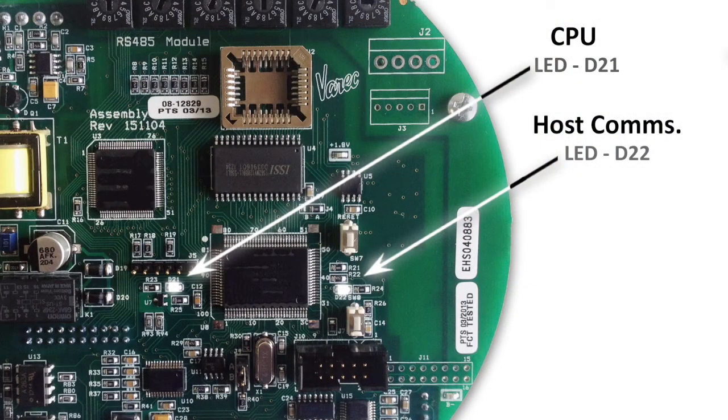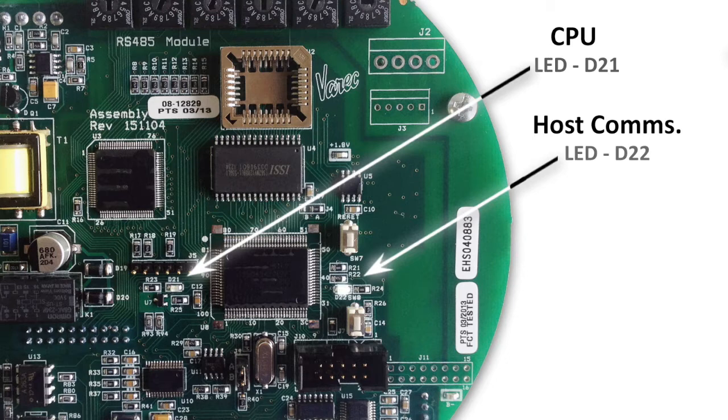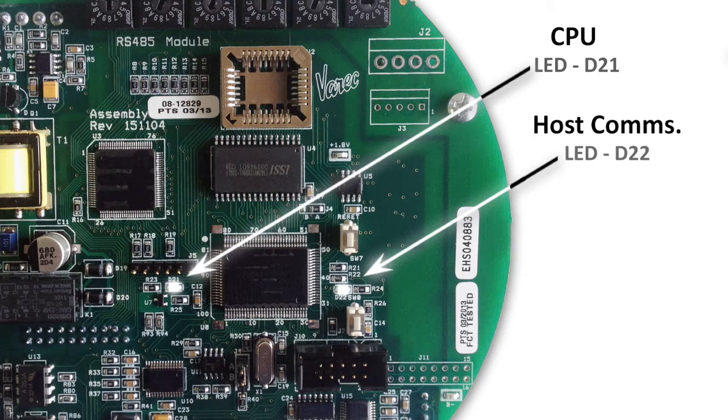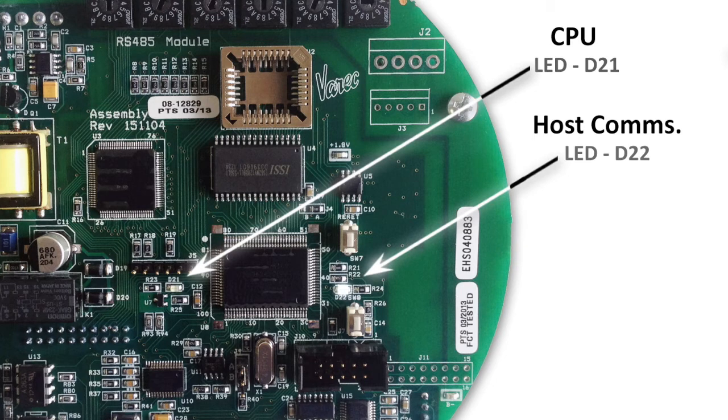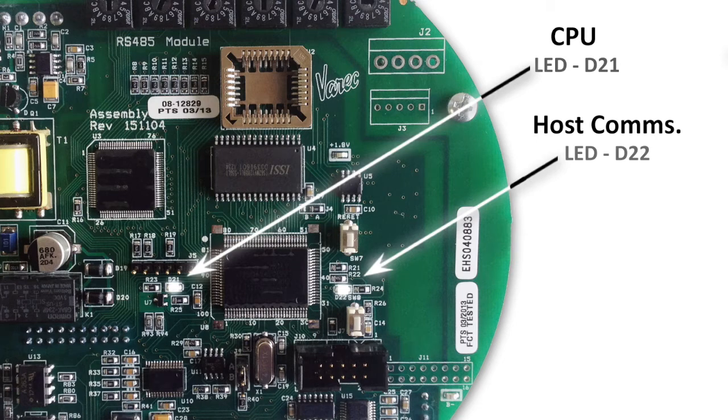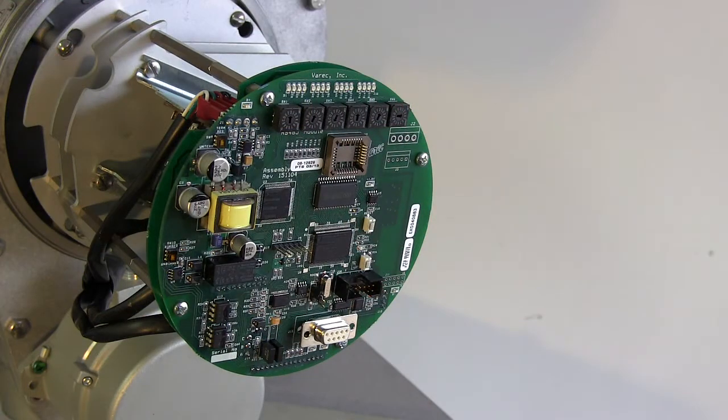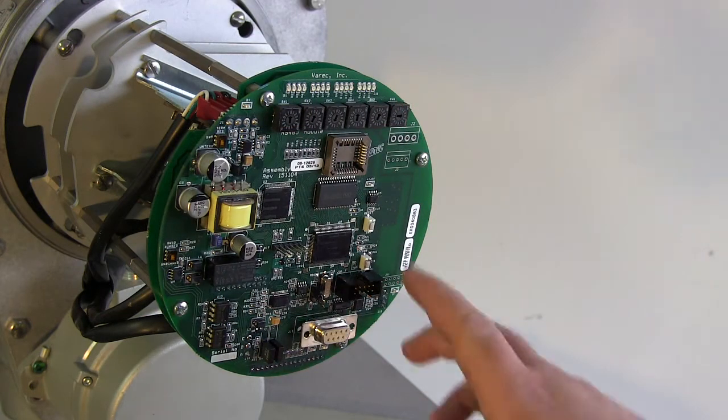At this point, it's good practice to check the host communications. LEDs 21 and 22 flash on and off when the transmitter is okay. If LED 21 does not flash, there is a problem with the CPU and you should contact Varec to return the unit for service. LED 22 flashes based on the poll rate from the host. If it is continually lit or not at all, then it is not communicating with the host system.